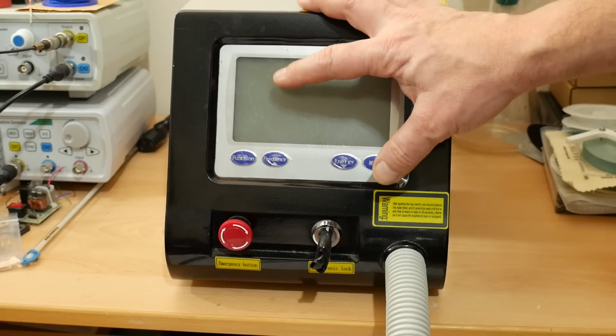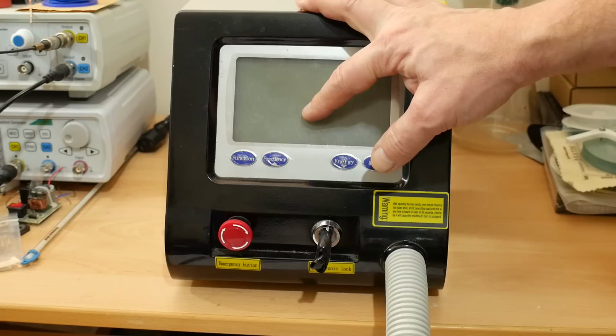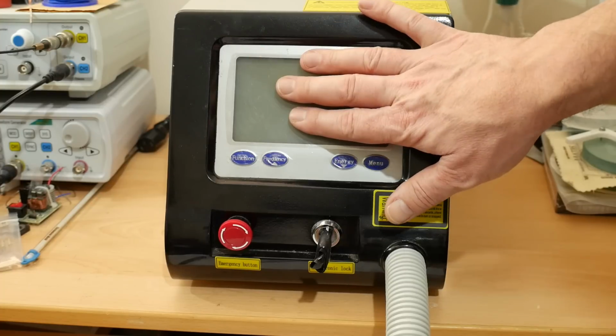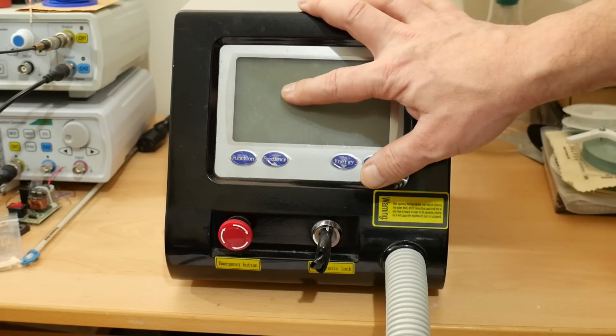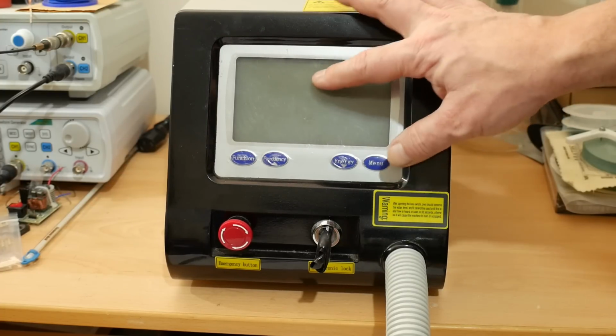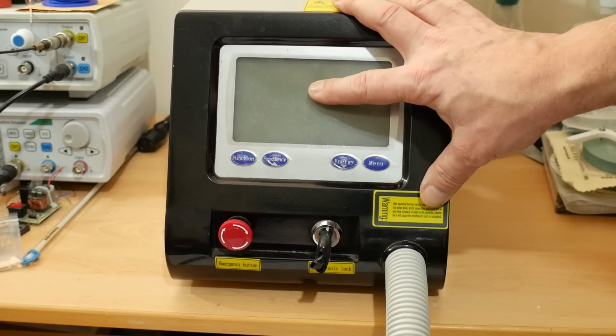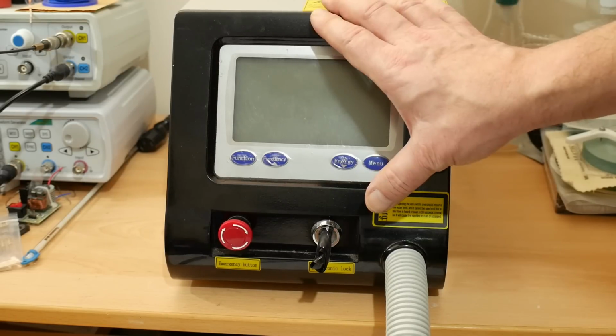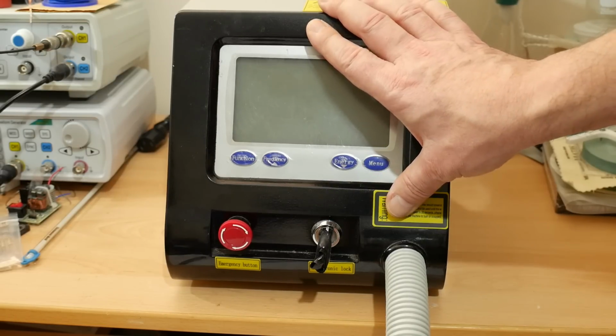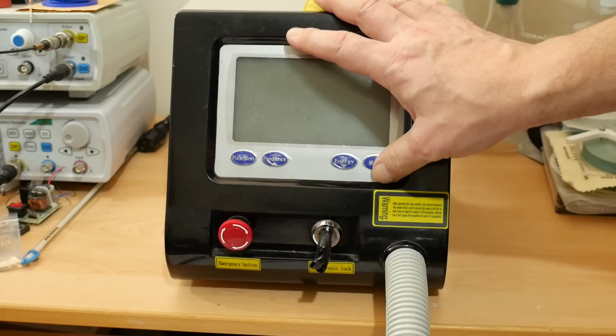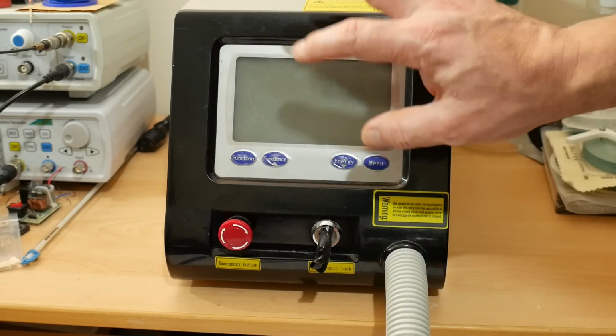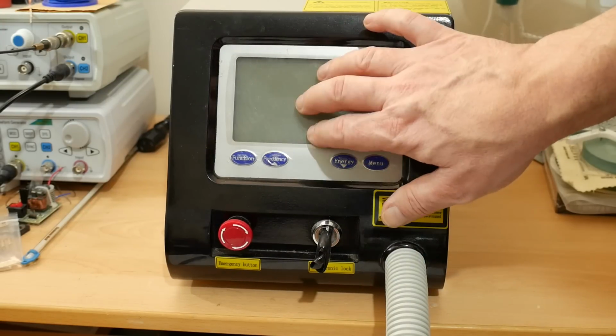The only reason I can think of that an arc would be struck inside the flash lamp is if the voltage is too high. We must be looking somewhere in the region of about 1,500 to 2,000 volts in order to cause that to occur. So the switch mode power supply is out of regulation. It's no longer being regulated, so it's just being let to run and charge the capacitor up as high as it wants.